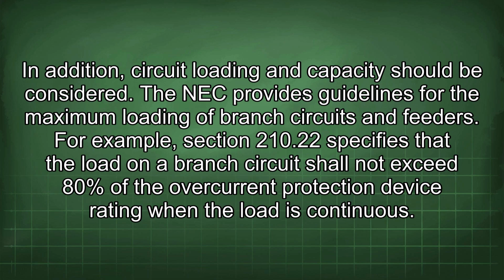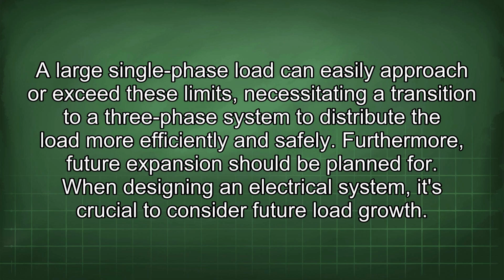For example, Section 210.22 specifies that the load on a branch circuit shall not exceed 80% of the overcurrent protection device rating when the load is continuous. A large single-phase load can easily approach or exceed these limits, necessitating a transition to a three-phase system to distribute the load more efficiently and safely.